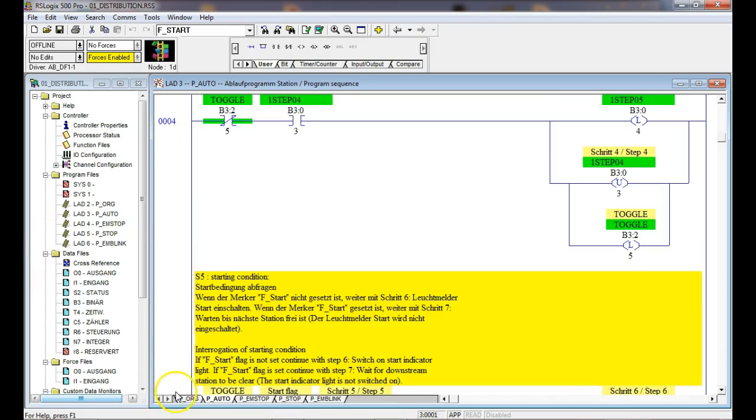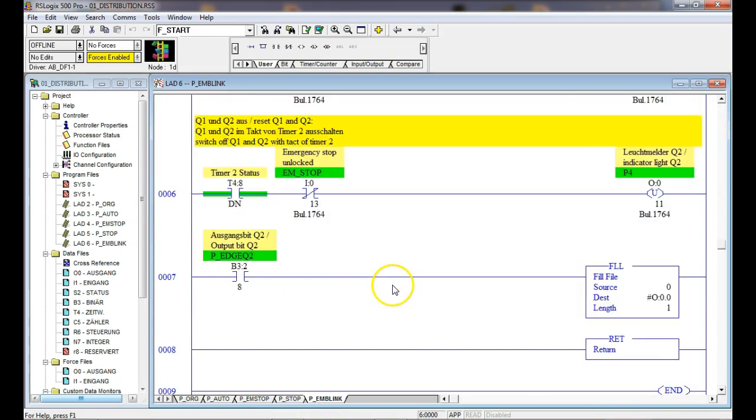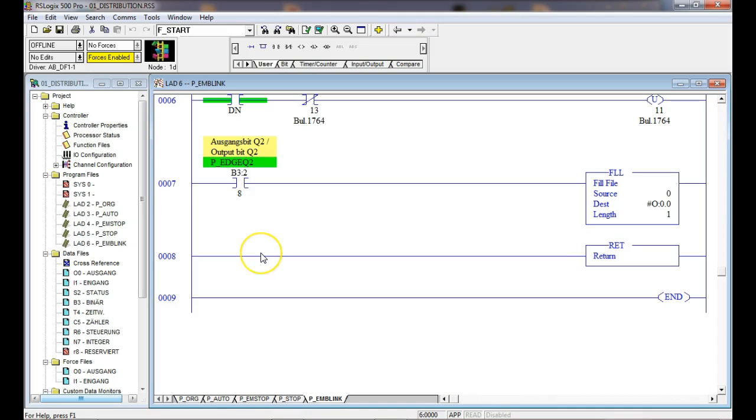So what we can do now is, if I want to troubleshoot just that module, all I have to do is come over here and put a line in here that takes away that return. And then now my program is just going to scan that module, right? And I can play around with that module as long as I want to and get it working. And then put the return back in there, and then it'll work as a subroutine instead of a module.